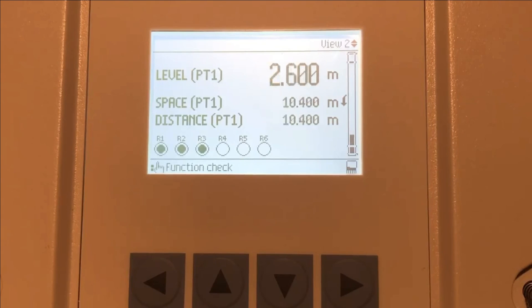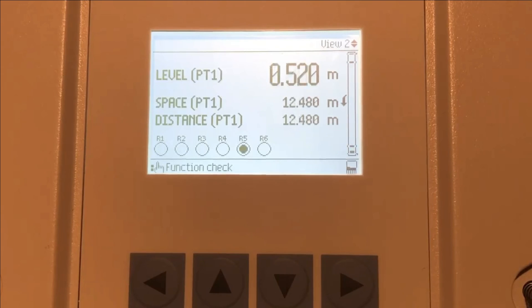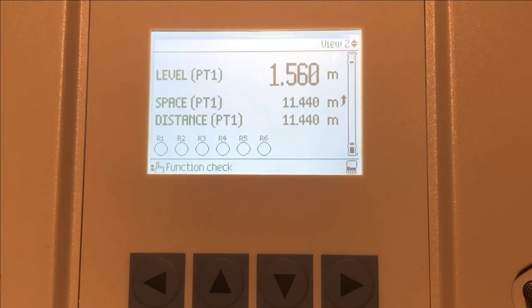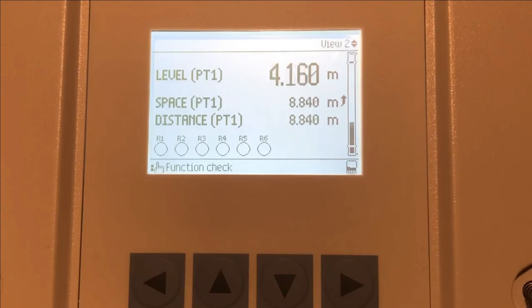So we can see the filling and emptying indicator on the screen as well. And there goes our pumps and there comes our low level alarm. And then we start ramping back up again. So a simulation is very quick and easy way to check your setup, make sure that everything's operating properly.